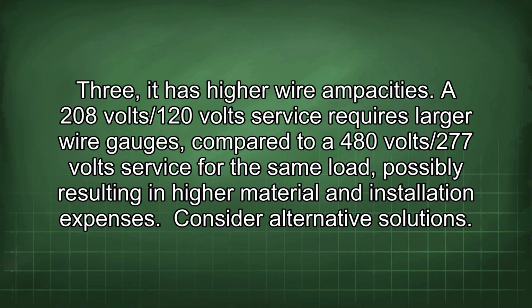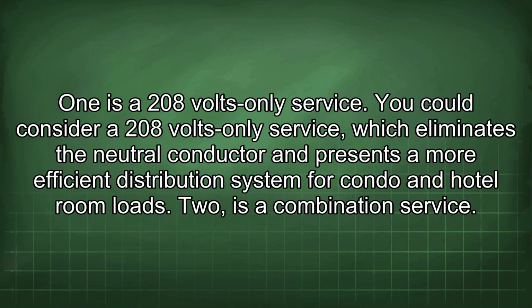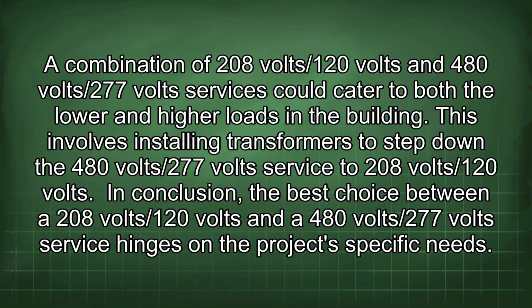Consider alternative solutions. 1 is a 208 volts only service. You could consider a 208 volts only service, which eliminates the neutral conductor and presents a more efficient distribution system for condo and hotel room loads. 2 is a combination service. A combination of 208 volts/120 volts and 480 volts/277 volt services could cater to both the lower and higher loads in the building. This involves installing transformers to step down the 480 volts/277 volts service to 208 volts/120 volts.